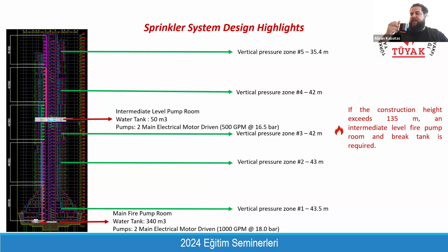But if your building height exceeds 130 meters, then you need to provide an intermediate level fire pump room to feed the upper floors, and it will be a challenge for your architectural design. You need to find a place at this higher level to locate the fire pumps and also water tanks. But these water tank capacities are relatively small compared to the main water tanks. These are only 50 cubic meters, so that will not cause a lot of problems regarding static design.